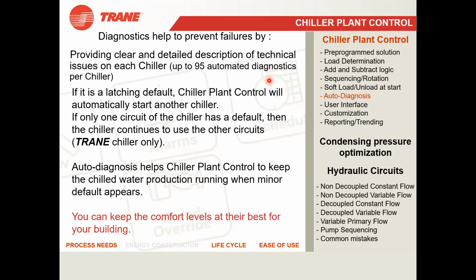Because of this auto diagnosis, suppose you get a latching defect. The CPC will not switch off the complete system. It will only start another chiller, bypassing that particular chiller, so your load is not affected at all. And if in any chiller only one circuit is affected, it will bypass that circuit, and the chiller will keep running with all other circuits. So all these kinds of facilities are there in the CPC.